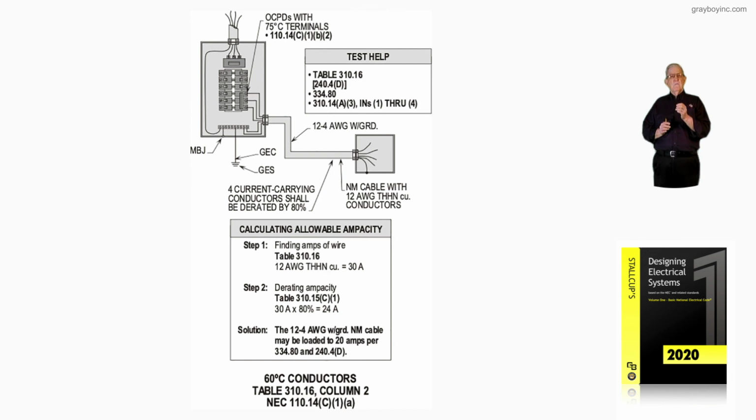And this can be fully reviewed by designing engineers by going to 110.14(C)(1), read that last, I believe it's the last sentence in there, that you can use higher temperature conductors to derate back, basically to usable 60 or 75, whatever your terminal ratings are. But you can put a nail in the coffin right quick by going to 334.80, and it's explained in detail.